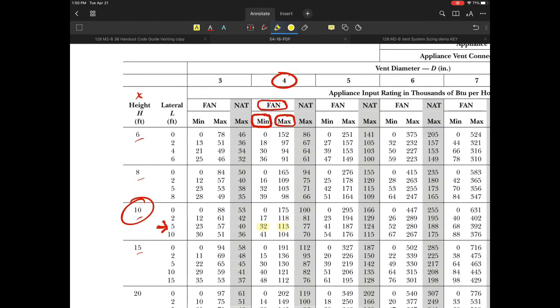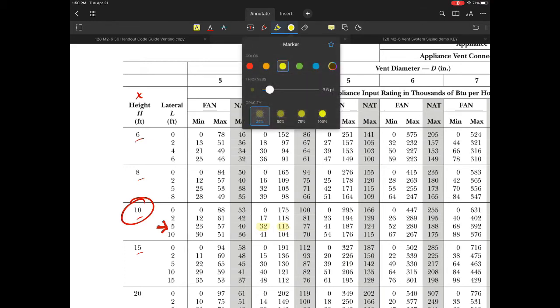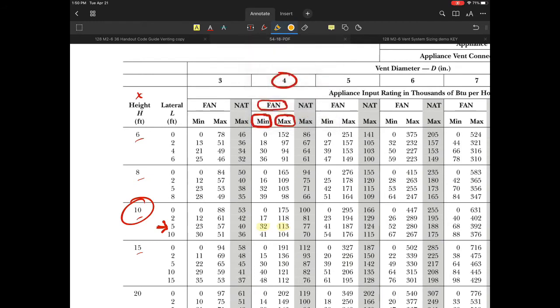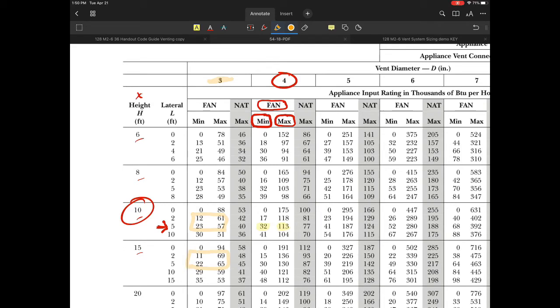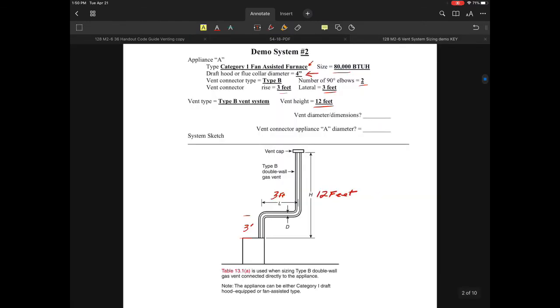To double-check if I could downsize to a 3-inch, looking at this region, at 57,000 we're at 80,000 BTU. It doesn't even pay to look at it. If I went up to 15 feet, there's only 8,000 BTU difference, so it doesn't apply.